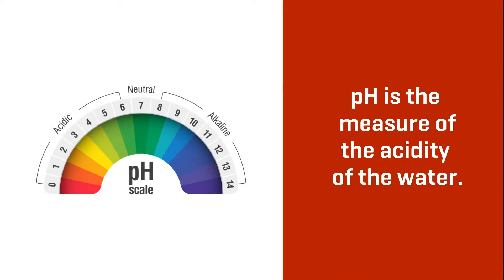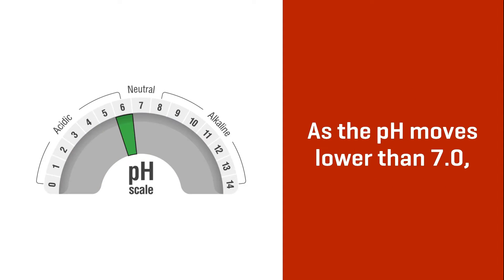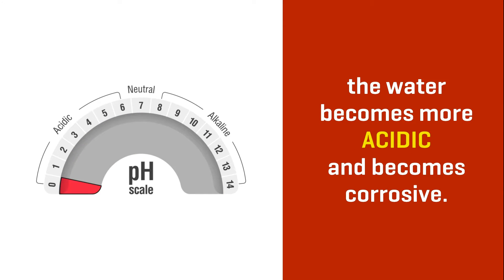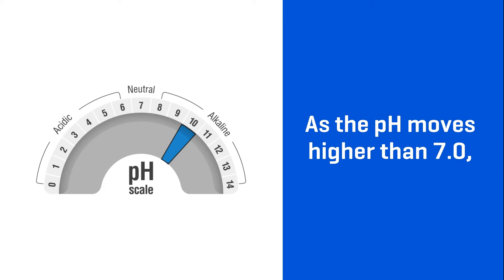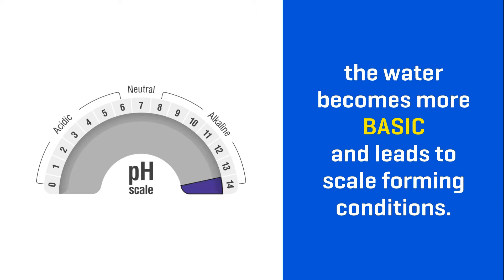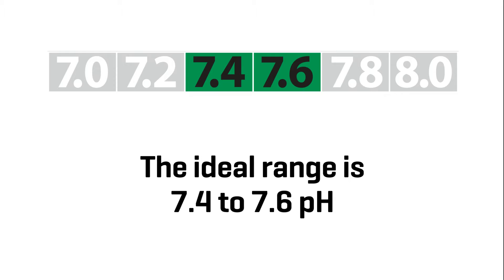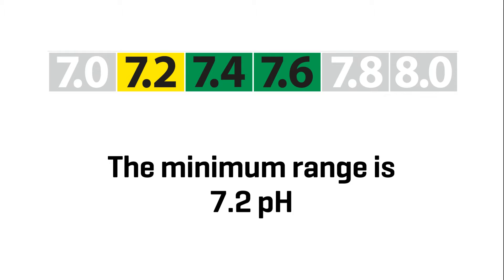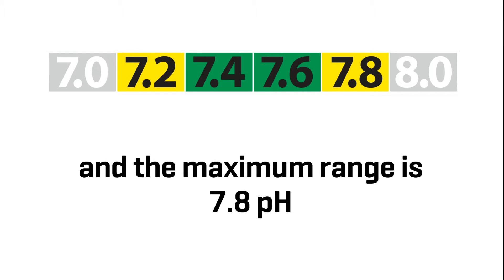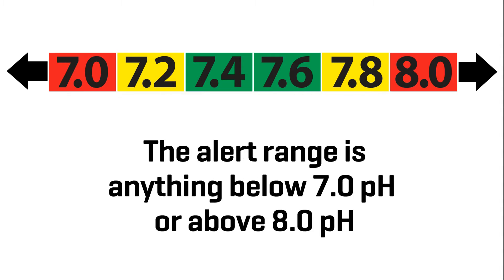pH is a measure of the acidity of the water. As the pH moves lower than 7.0, the water becomes more acidic and becomes corrosive. As the pH moves higher than 7.0, the water becomes more basic and leads to scale-forming conditions. The ideal range is 7.4 to 7.6 pH. The minimum range is 7.2 pH, and the maximum range is 7.8 pH. The alert range is anything below 7.0 pH or above 8.0 pH.